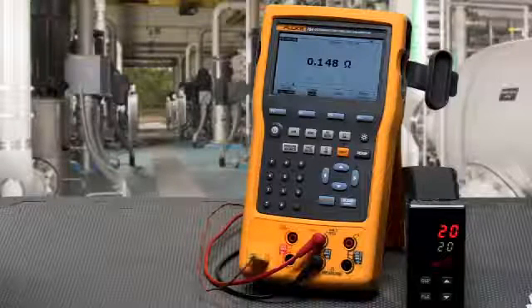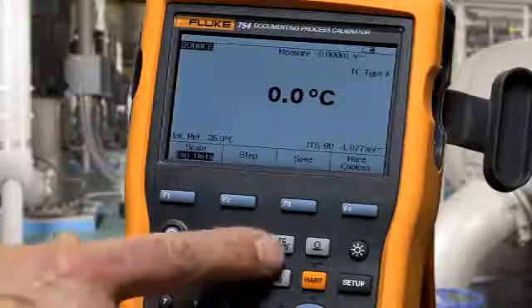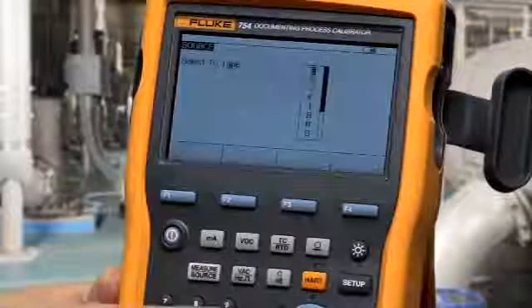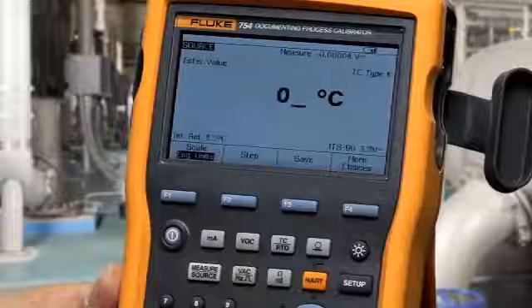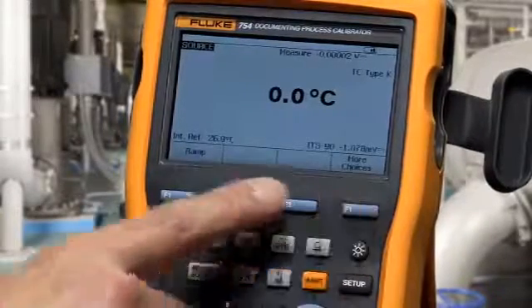First, we'll show ramping the output. First, you must get to the source screen, then select the function. In this case, we're selected for a type K thermocouple. Type in your temperature value. Select more choices twice, and then select ramp.